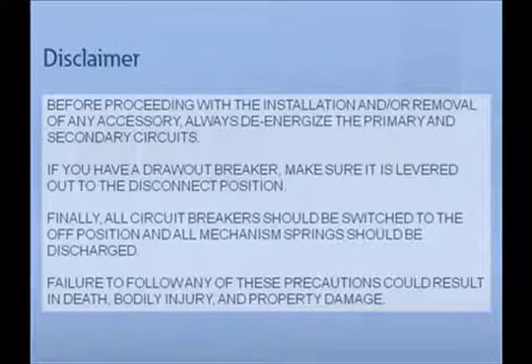Before proceeding with the installation and/or removal of any accessory, always de-energize the primary and secondary circuits. If you have a drawout breaker, make sure it is levered out to the disconnect position. Finally, all circuit breakers should be switched to the off position, and all mechanism springs should be discharged. Failure to follow any of these precautions could result in death, bodily injury, and property damage.